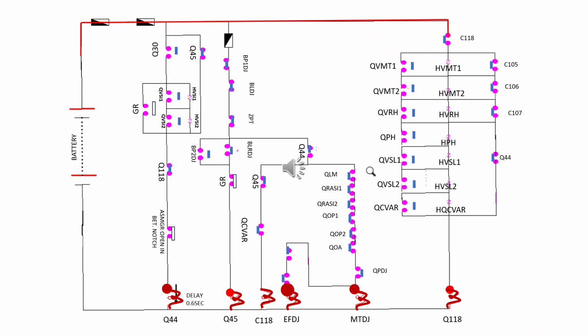So Efdj is for closing the DJ, and Mtdj is for maintaining it, and if any of the safety relays trips, then it will de-energize the Mtdj, and Mtdj will allow the left side chamber air pressure and the DJ will open. This is for protection. So I think you have a basic idea about the controlling system with this 110 volt. With this 110 volt DC, we are controlling 25 kV as well as other voltage systems, which are harmful for our body. So in this way, we are using two circuits, power circuit and control circuit.